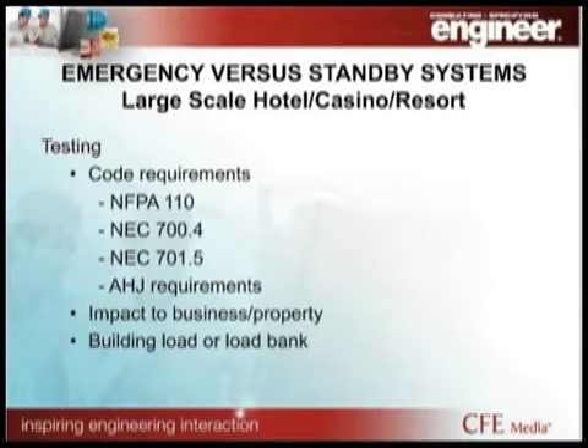Testing it under load, taking it under full transfer of its equipment, and then having a live load bus. A live load bus now serves as your load bank, so you can definitely get your engines up to the capacity that's required to ensure that you're meeting the minimum load requirements NFPA 110 dictates for minimal capacity for testing under load.